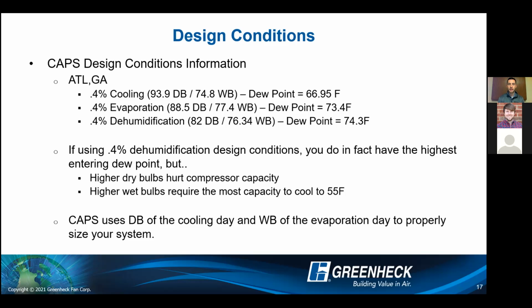So while the 0.4% dehumidification design conditions do have the highest dew point, which you think you would want to size around, there are a couple things to think about. First one being that higher dry bulbs actually hurt compressor capacity. So if you look at the 0.4% cooling, that actually has the highest dry bulb. On top of that, the higher wet bulbs require the most cooling capacity to actually cool down to that 50, 55 degree Fahrenheit. And if you look at the evaporation, that has the highest wet bulb. So what we do is we actually use the dry bulb of the cooling day and the wet bulb of the evaporation day to properly size your system.